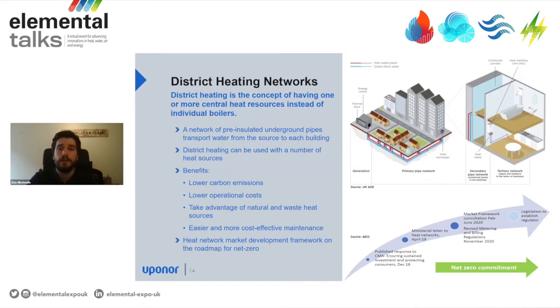The main benefits of this concept are that the system produces less carbon emissions and leads to lower operational costs. Maintenance is easier as the plant room is external to the building, which also leads to lower maintenance costs. Last but not least, district heating networks can work in conjunction with natural and waste heat sources.